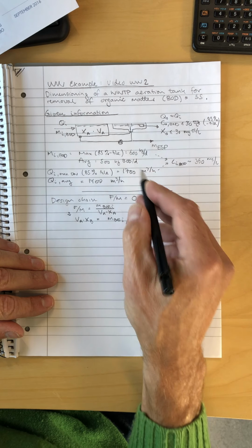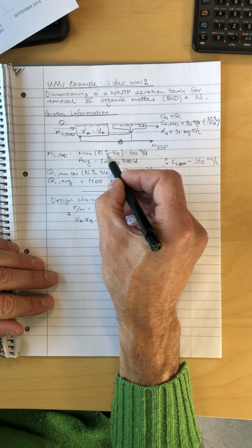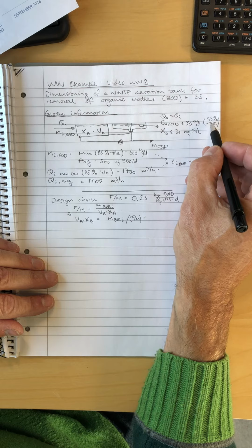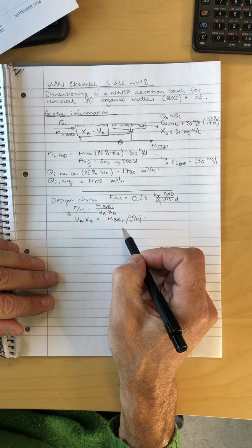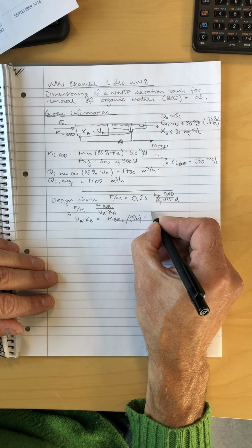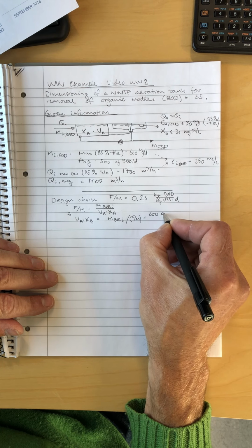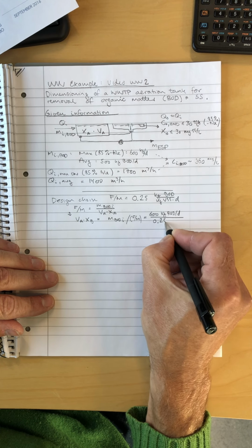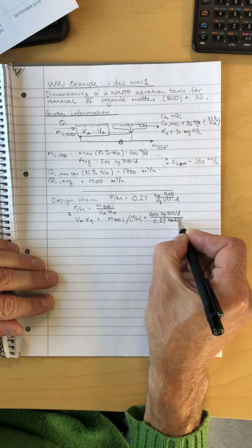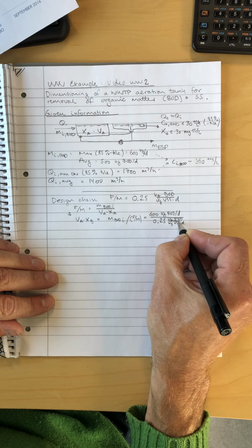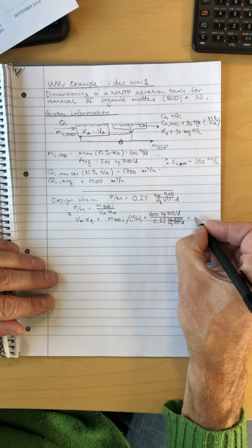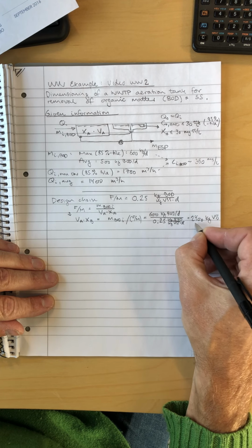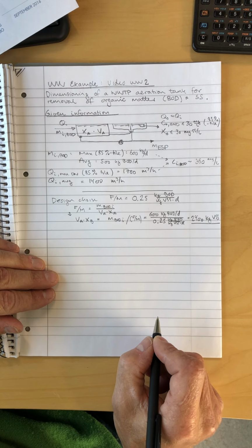I've got 600. I will use the 85 percentile for the design purpose because at that load I should be able to perform according to the requirement, because I'm only allowed to exceed the requirement about 15% of the time. So that will be an appropriate number: 600 kilogram of BOD per day, and the FM ratio being 0.25 kilogram BOD per kilogram VSS per day, and the output here will be 2400 kilogram VSS. So this is the mass of sludge I need in my system.